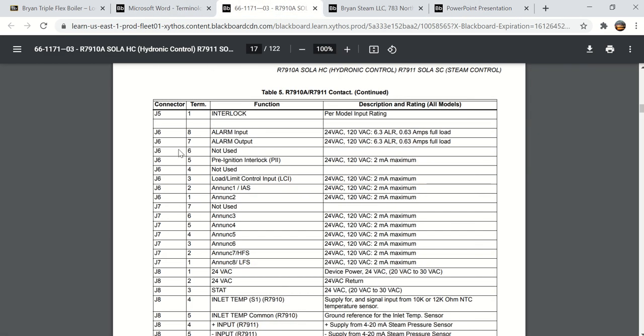So when we look at J6 terminal number 2, it is annunciate 1, and it can be either 24 volts or 120 volts up to 2 milliamps maximum. Really, it's just a power going to that terminal, and that input, you can see you've got annunciate 2, 3, 4, 5, 6, 7, 8. Those annunciation inputs are what the controller uses to determine whether or not that control is either closed or open.